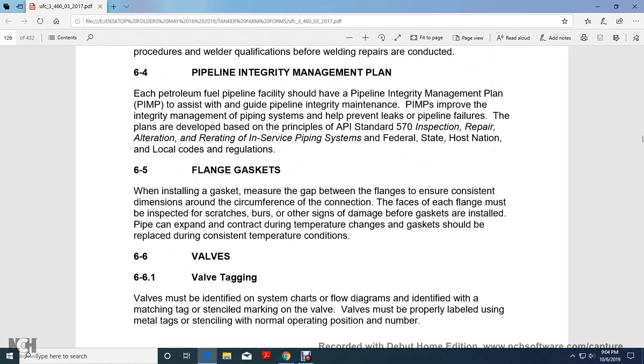6.5, flange gaskets. When installing the gasket, measure the gap of the flange to ensure it is consistent with the dimension. The circumference of the connection face of each flange must be inspected for scratches, burrs, or other signs of damage before the gaskets are installed. The pipe can expand and contract during temperature change. Gaskets should be replaced during consistent temperature conditions.